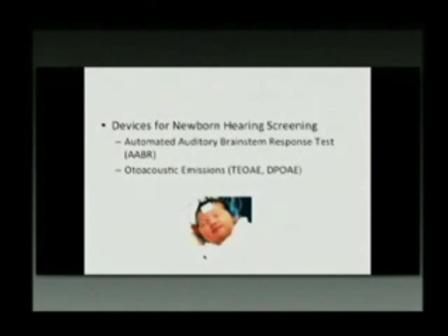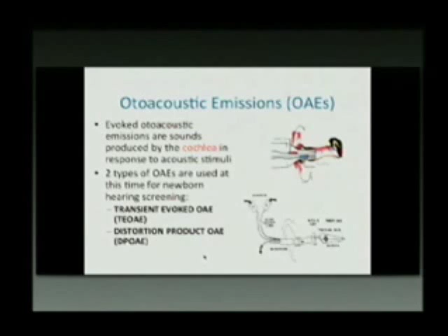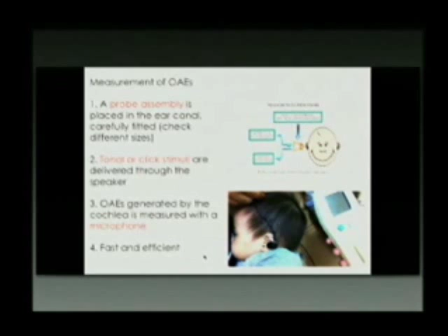Otoacoustic emissions are sounds produced by the cochlea in response to acoustic stimuli. There are 2 types, your transient evoked and your distortion product. The main difference between the two is that with the transient evoked, you have 1 speaker producing clicks or broadband signals, and for your distortion product, you have 2 speakers, each one producing a pure tone. This is done on the baby by placing a probe assembly in the ear canal from which tonal or click stimuli are presented, and a microphone which picks up the OAEs generated in the cochlea. This is a very fast and efficient test, taking only about 1 to 2 minutes for both ears.